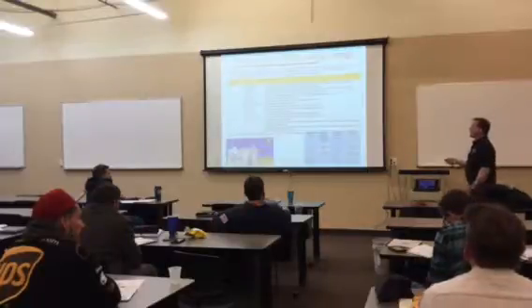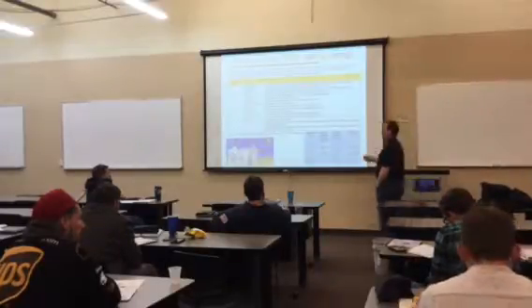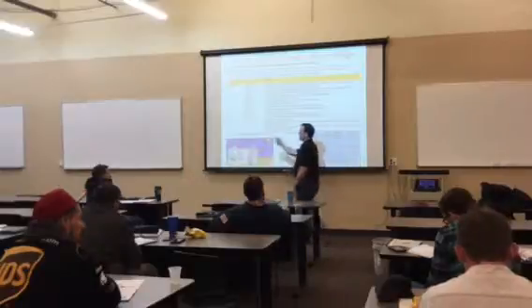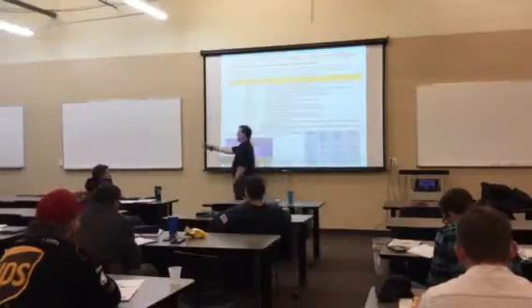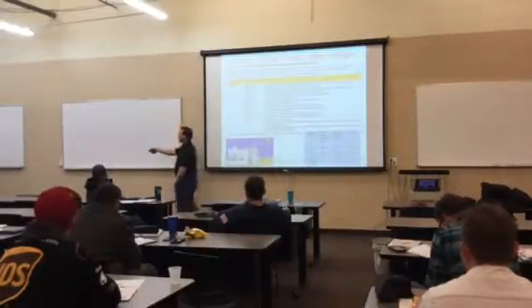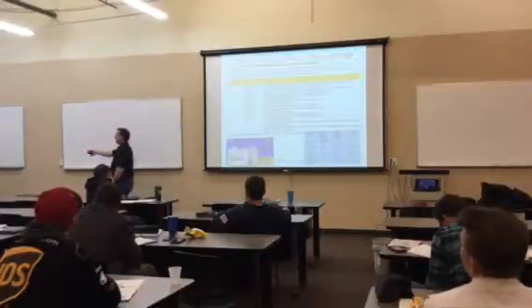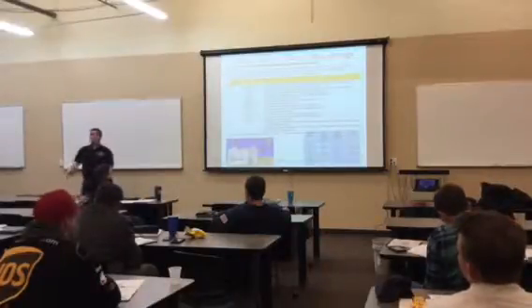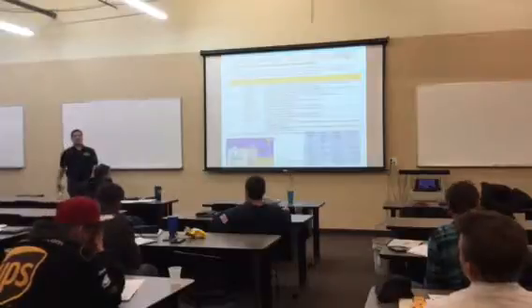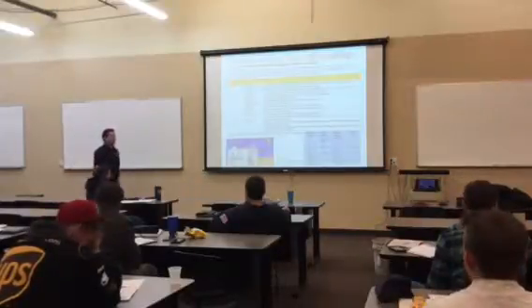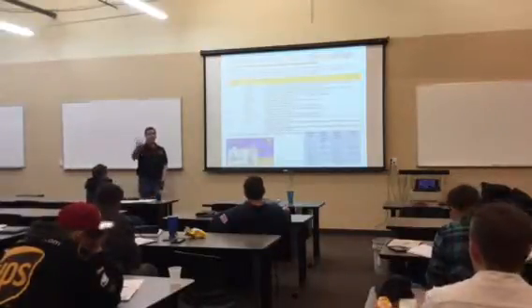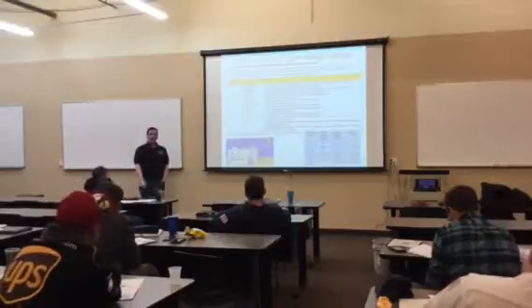Category 2, single-phase receptacle connected loads. Anything plugged into the wall, boom, right there. Those are category 2. And working inside of this TP, that'd be category 2. Inside of that receiver, category 2. Inside of a power tool, cat 2. Anything plugged into the wall. Your humidifiers, those humidifiers we're talking about on Monday, cat 1, cat 2.